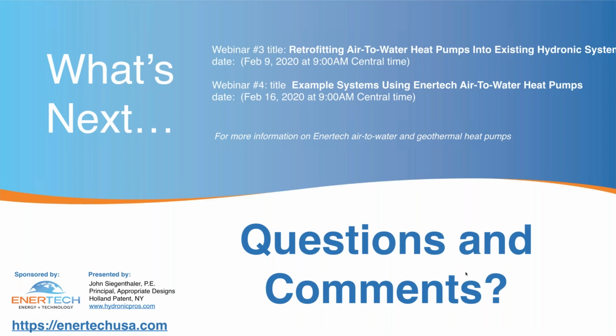Again, it's going to be chilled water cooling, but as we looked at today, we could do that with a central air handler. We could do it with area by area or room by room console type units. And we have the advantage that we can tie domestic water into that heat pump. The heat pump is providing domestic hot water, whereas a standard AC system would not be doing that for you.